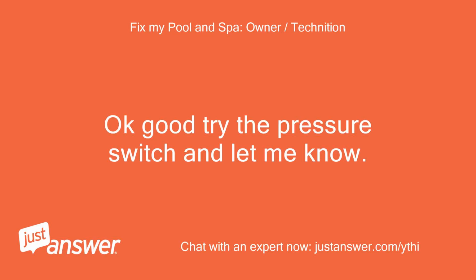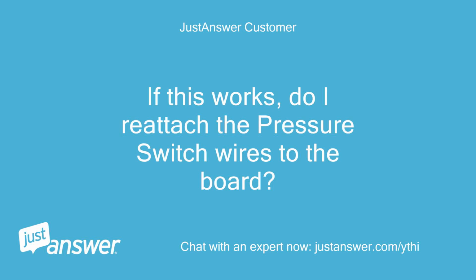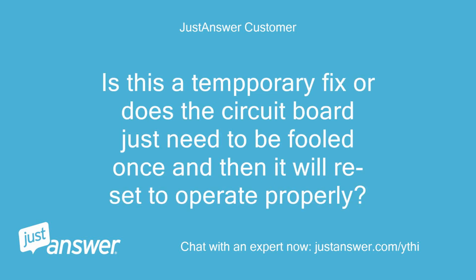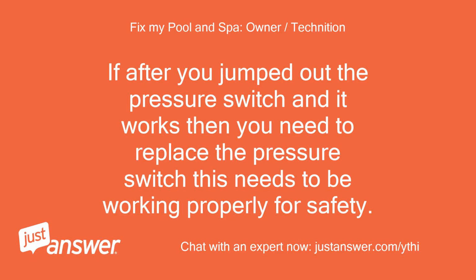Okay, good. Try the pressure switch and let me know. If this works, do I reattach the pressure switch wires to the board? Is this a temporary fix, or does the circuit board just need to be fooled once and then it will reset to operate properly? If after you jumped out the pressure switch it works, then you need to replace the pressure switch. This needs to be working properly for safety.